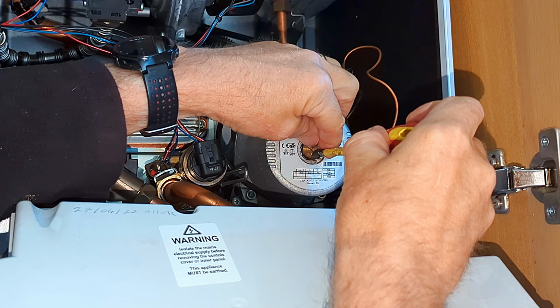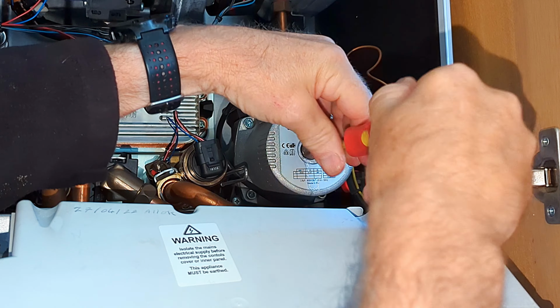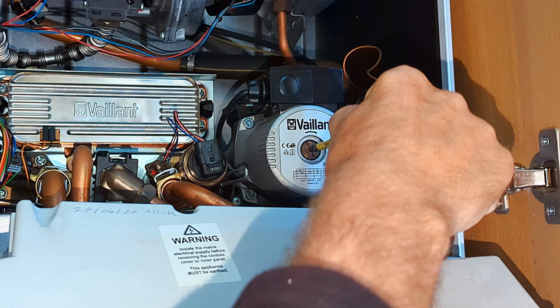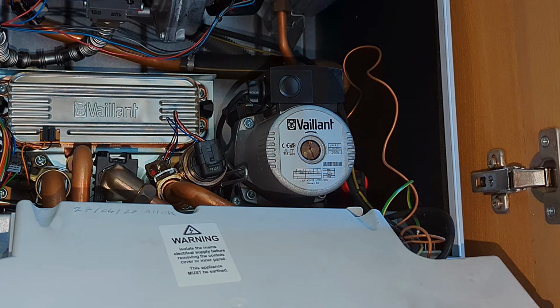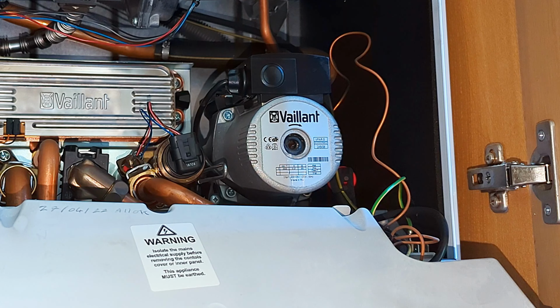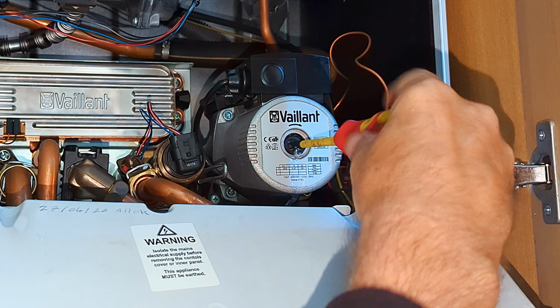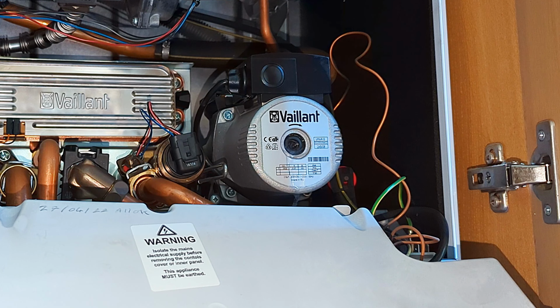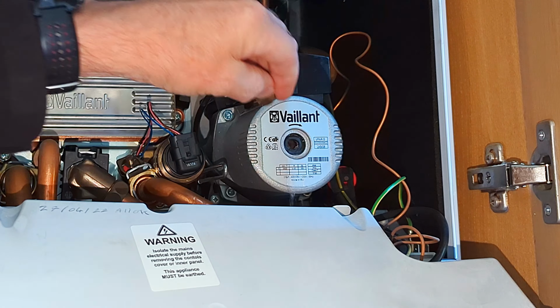And you shouldn't be able to stop the pump from spinning. I'm always really careful when I do this because I might get lots of water pouring out, which may be scalding hot. Now if the pump isn't running, I can put my screwdriver into that hole there, put it on the shaft of the pump, and rotate the shaft with my screwdriver. Obviously I need to do this when the boiler is trying to run, because the pump will only be spinning when the boiler is in operation.